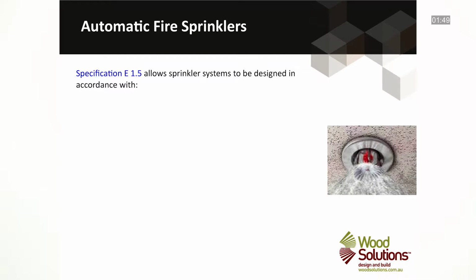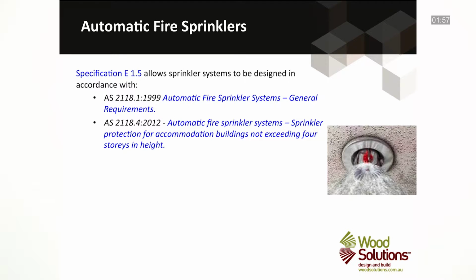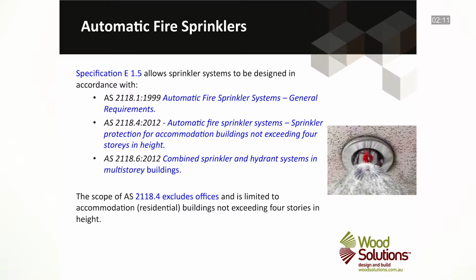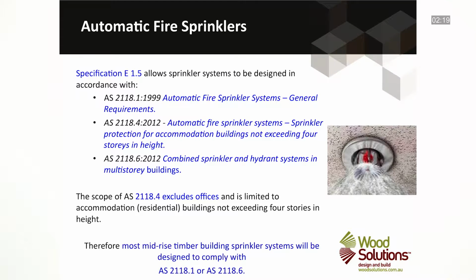Specification E1.5 allows sprinkler systems to be designed in accordance with 3 Australian standards: AS2118.1, Automatic Fire Sprinkler Systems, General Requirements; AS2118.4, Automatic Fire Sprinkler Systems, Sprinkler Protection for Accommodation Buildings not exceeding 4 stories in height; and AS2118.6, Combined Sprinkler and Hydrant Systems in multi-storey buildings. The scope of AS2118.4, however, excludes offices and is limited to residential accommodation buildings not exceeding 4 stories in height. Therefore, most mid-rise timber building sprinkler systems will be designed to comply with AS2118.1 or AS2118.6.